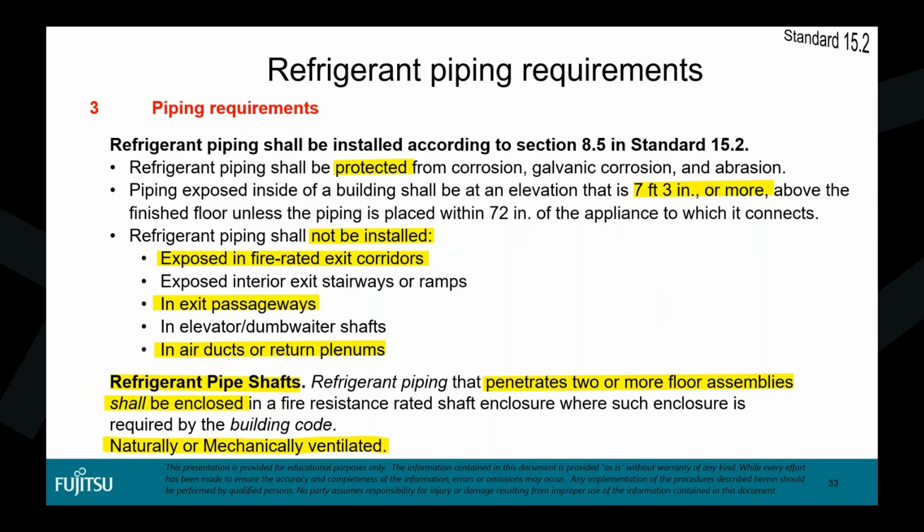The word exposed is interesting there. It can't be exposed in the fire-rated exit corridors, but it can probably be installed if it's not exposed in that corridor. The word exposed, you need to think through that a little. Can't be in air ducts or return plenums.